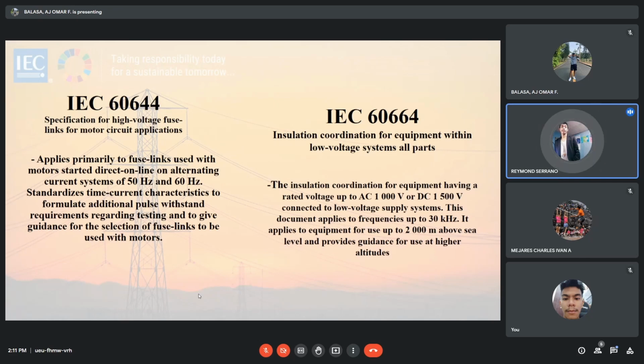When motors are used with assisted starting, this specification can also be applied, but particular attention should be paid to the selection of the rated current of the fuse link, and the manufacturer of the fuse link should preferably be consulted. The purpose of this standard is to standardize time-current characteristics, to formulate pulse withstand requirements regarding testing, and to give guidance regarding the selection of fuse links intended to be used with motors.